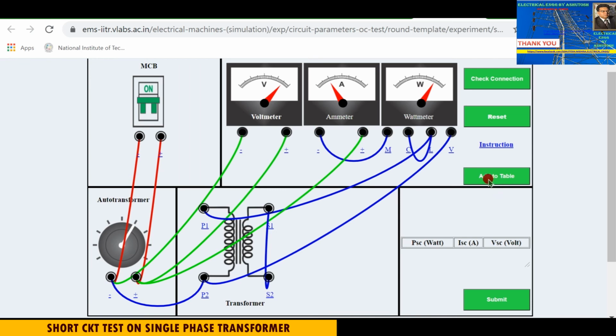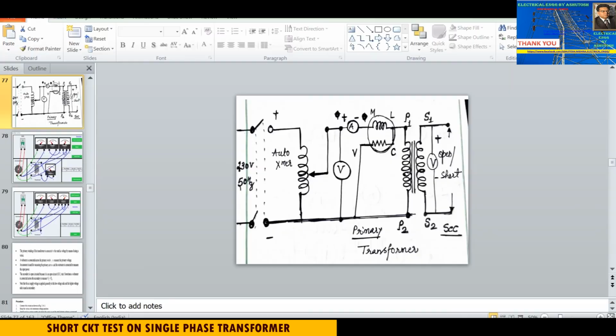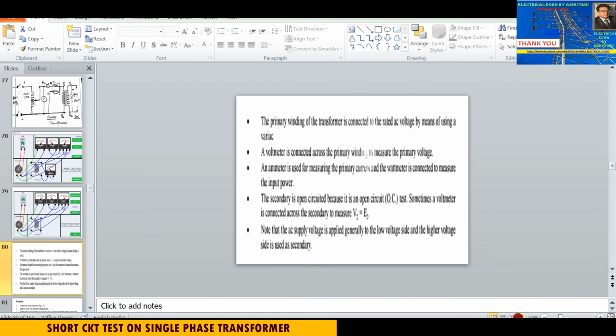Click add to table and you can see 11, the short circuit voltage VSC. This is VSC, this is ISC, and this is WSC. This is the reading of the short circuit voltage during the short circuit test. This is the short circuit current, 4.5 ampere ISC, flowing. That is the rated current of the transformer. And this is the copper loss shown by the wattmeter, 37.5 watt. So you can note it down and calculate all the parameters by following these formulas.